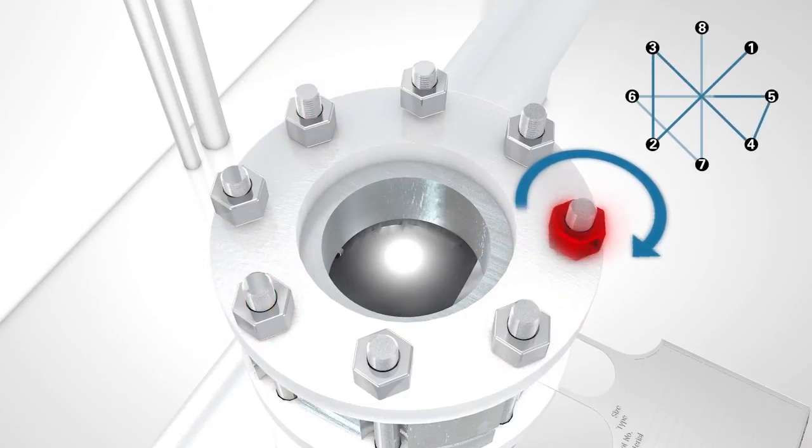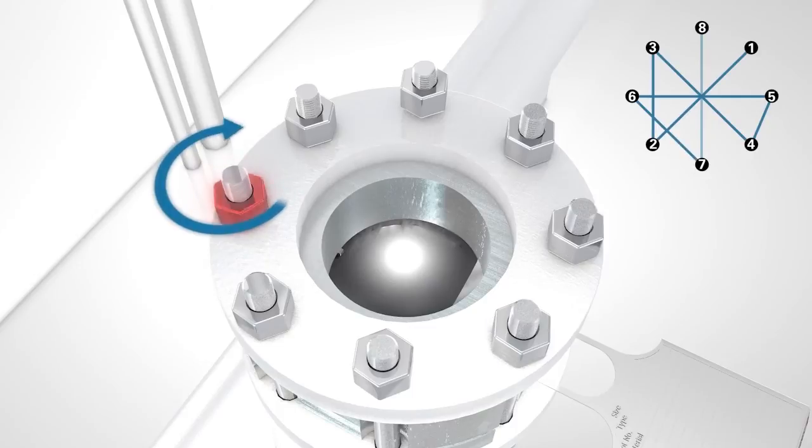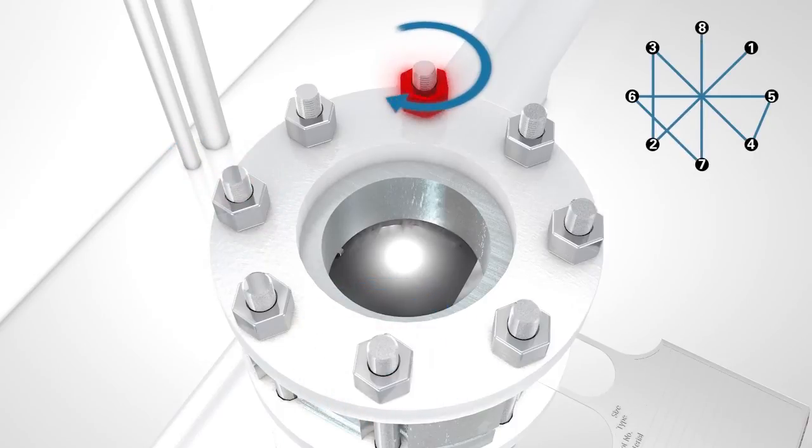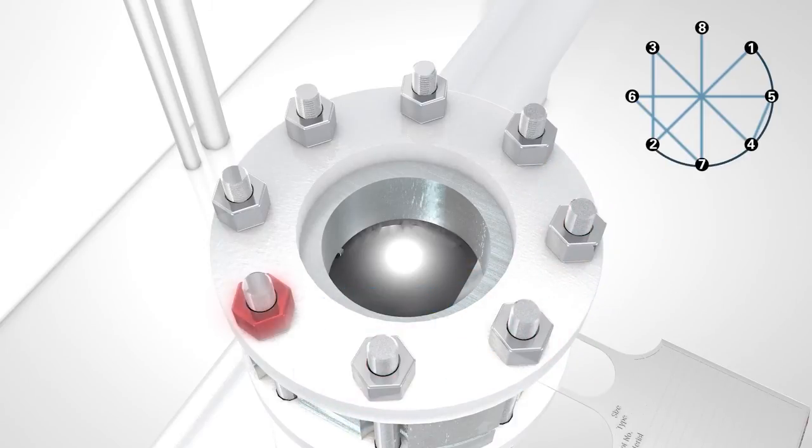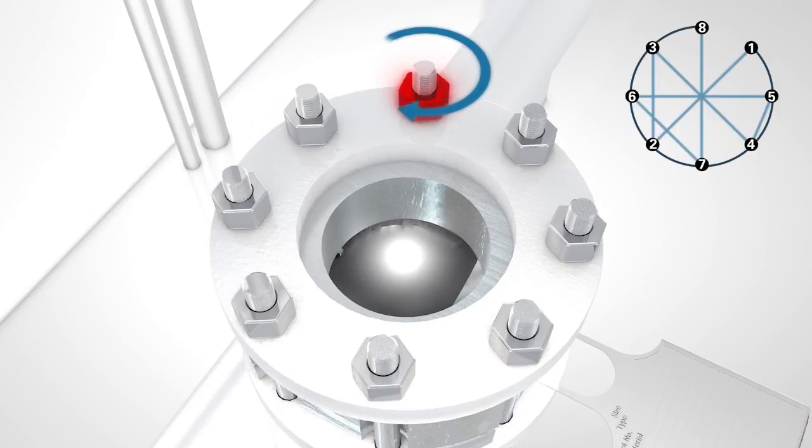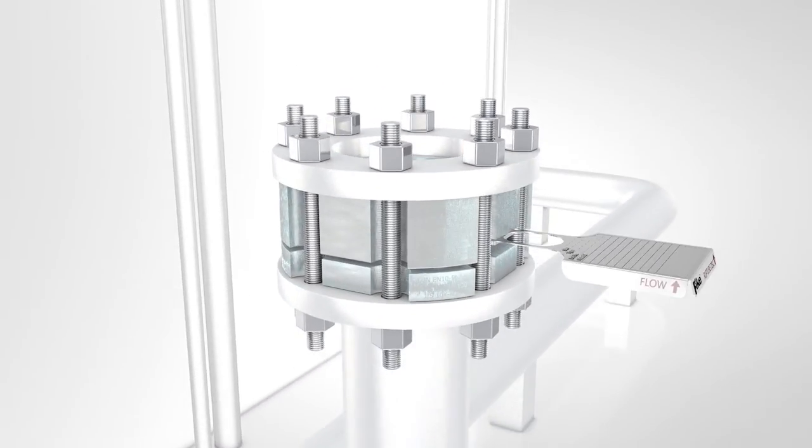After each torque step, check the gap between the base and hold-down to be sure it is still equal. After the final torque step has been completed, make one revolution around the flange to ensure each stud has received the correct amount of torque.